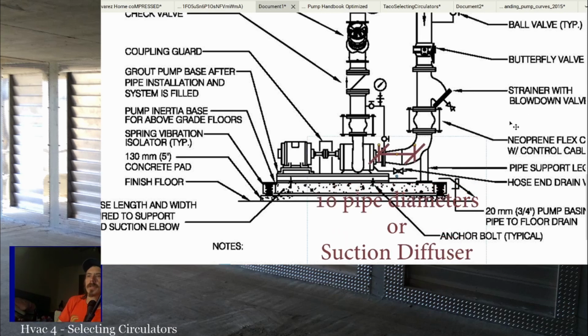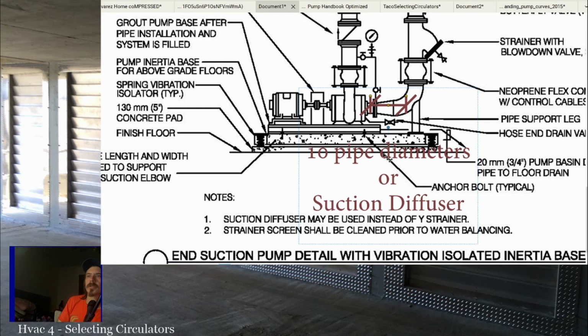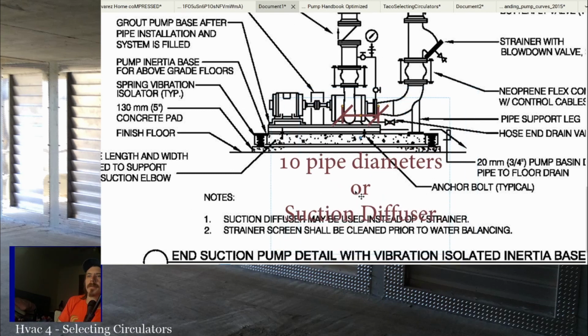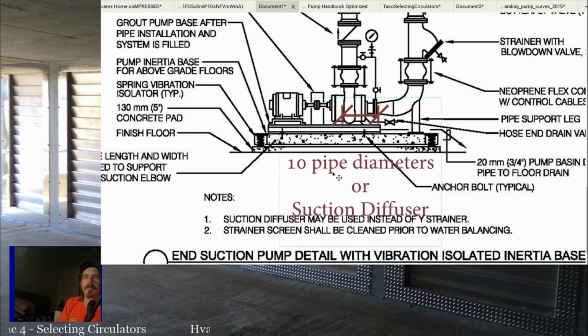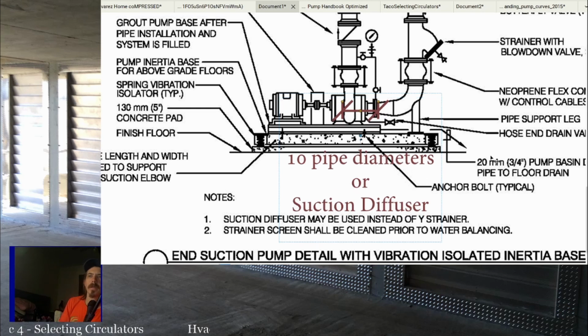All right, so for some reason you're dealing with a large pump, you can't have 10 pipe diameters, then you'll put what's called a suction diffuser on it. All right, and a suction diffuser just evens out the flow. It's basically like turning vanes for a pump. Okay, so if you cannot maintain that 10 pipe diameters before the pump, then you put in a suction diffuser on there.